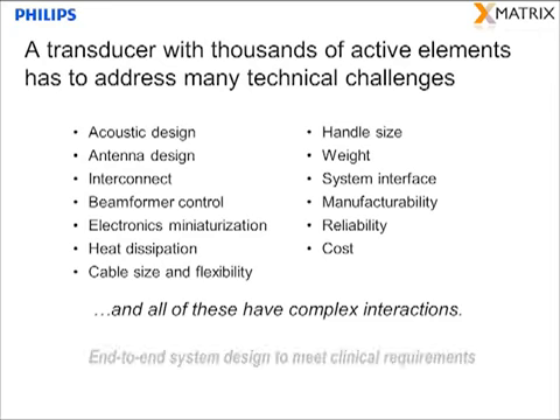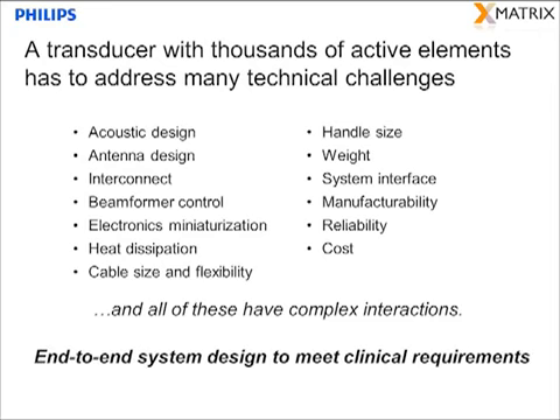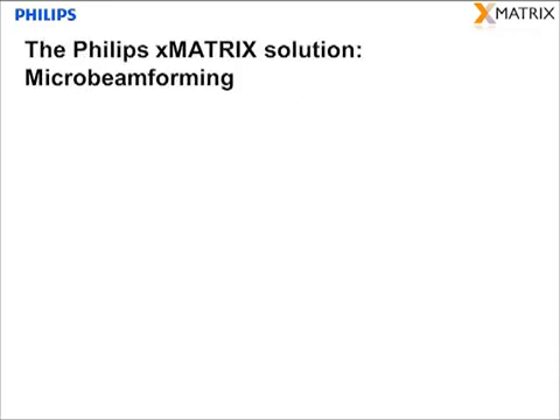The only way to be successful is to do an end-to-end system design from the front of the lens to the display, targeted at meeting the clinical requirements. The Philips xMATRIX solution is a technique we call microbeamforming, putting part of the beamformer in the transducer.